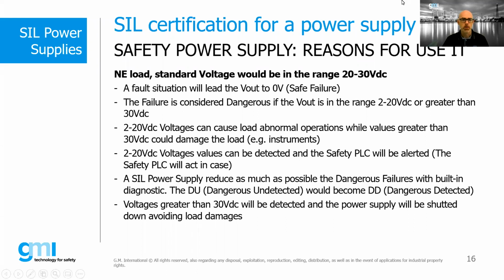In fact, if an anomalous output condition is detected by the safety power supply diagnostic, it brings the output to 0 volts, which represents the safe fault condition. Plus, a fault transistor alerts the PLC system, which can act as per specification. Even in case of a safety power supply output overvoltage condition, the internal diagnostic activates the redundant protection system for limiting the output voltage, which brings the latter to 0 volts. This means a safe fault condition.